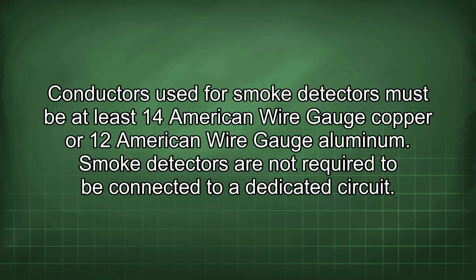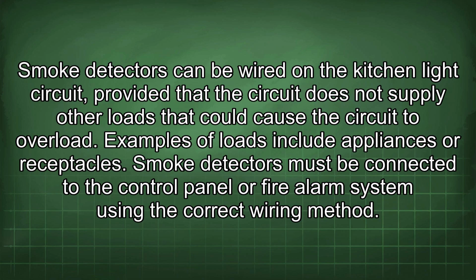Conductors used for smoke detectors must be at least 14 American wire gauge copper or 12 American wire gauge aluminum. Smoke detectors are not required to be connected to a dedicated circuit. Smoke detectors can be wired on the kitchen light circuit, provided that the circuit does not supply other loads that could cause the circuit to overload. Examples of loads include appliances or receptacles.